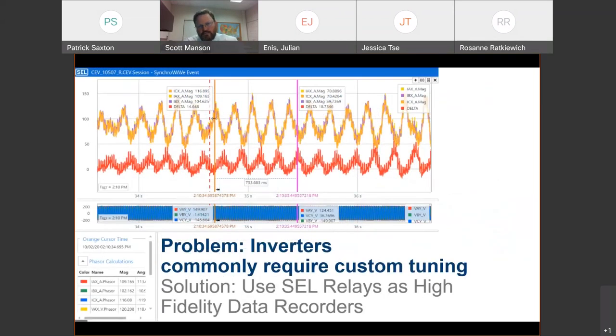Next challenge. There's a lot of custom tuning required. I'll give you an example. In a single inverter, there can be many more settings than a protective relay, thousands and thousands of configurations. Let me give you some examples. What is the synthetic inertia? What is the time constant of the filter on the synthetic inertia? What is the impedance compensation you're using? What are the 200 or 300 different gains for all your cascaded PID loop controls in that inverter? Ouch. That's a lot of places to make a mistake. That complexity is reducing reliability. This is creating a fragile grid.